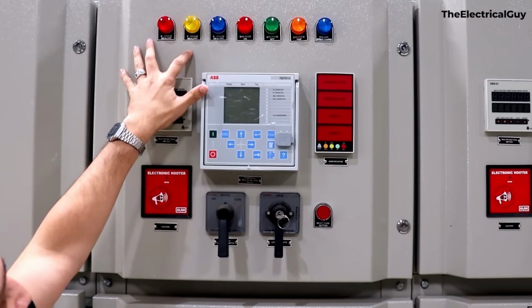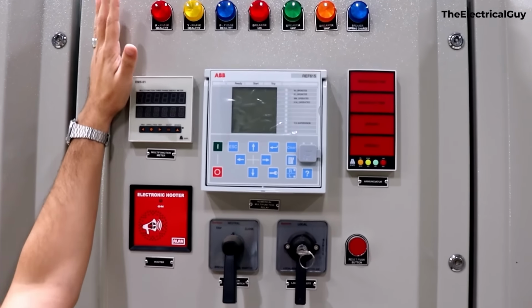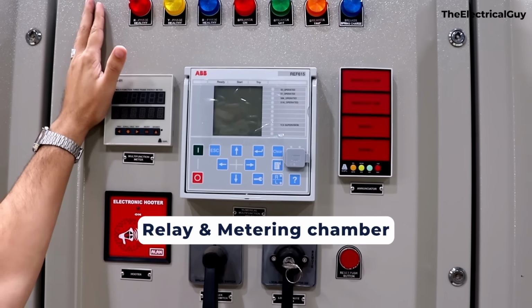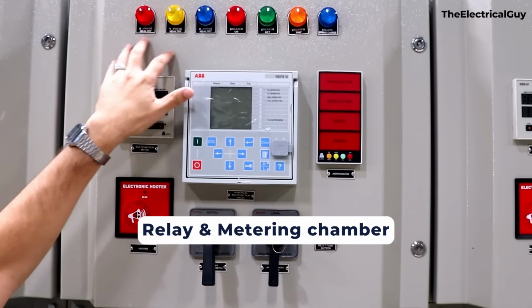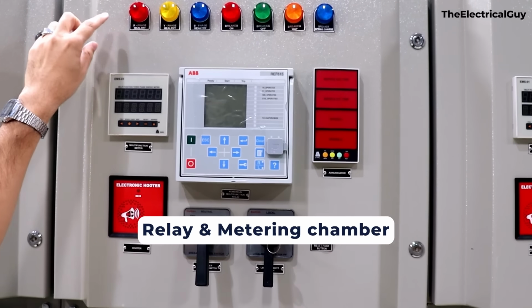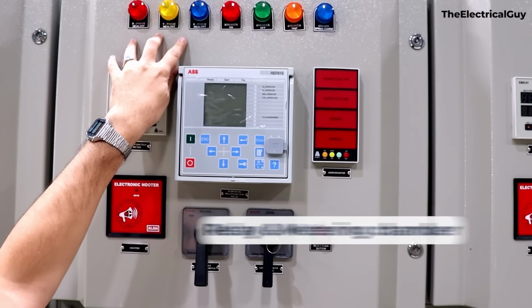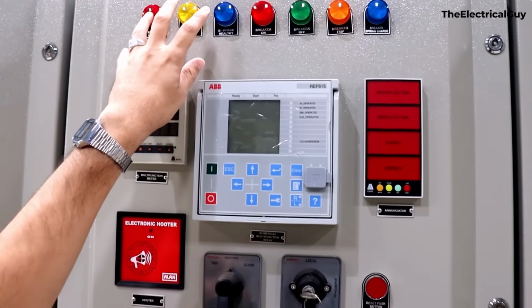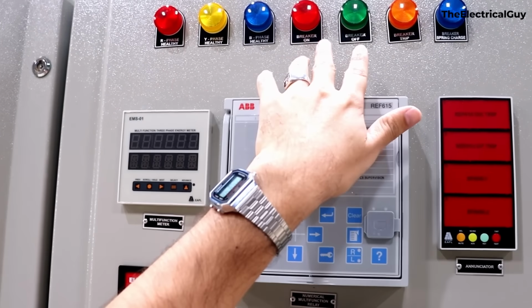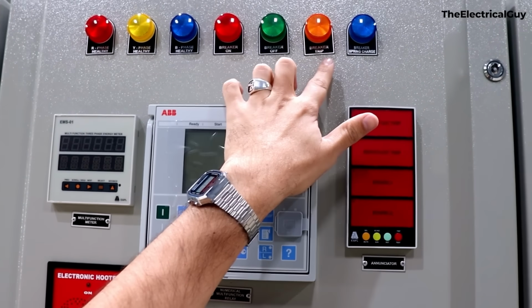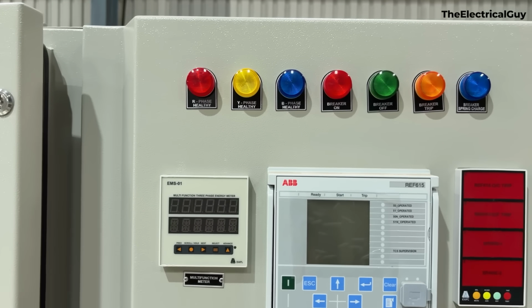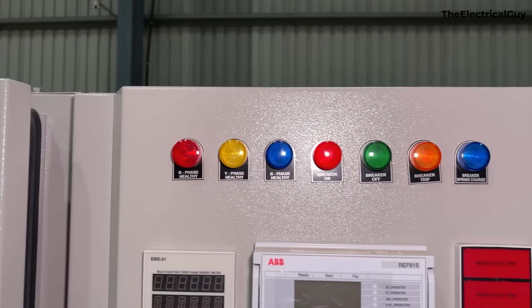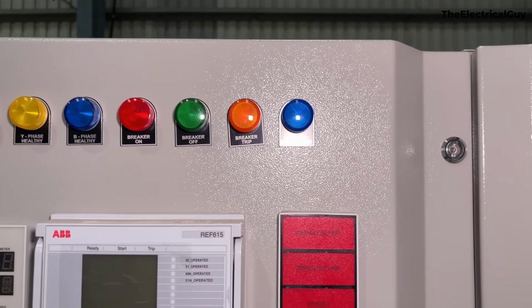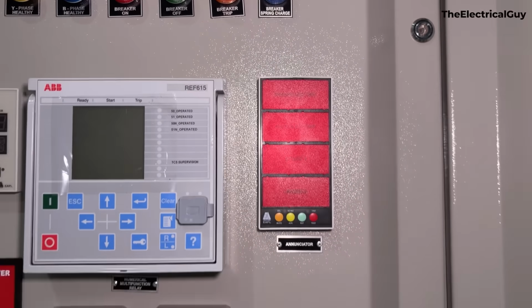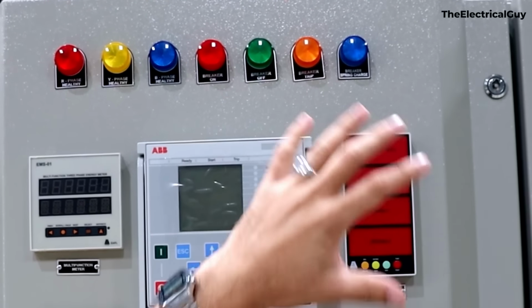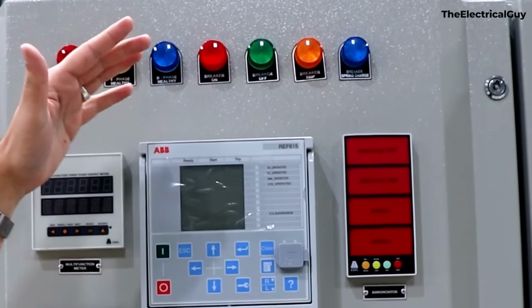Alright, so here are the indications, and before we go into the indications, this is also called the relay and metering chamber along with the low voltage chamber. So first you can see on top we have different indications. We have R, Y and B phase healthiness, so that means the voltage is available there and they are perfectly working fine. Then these are the indications about the breaker. In fact, the fourth also. You see the first one is breaker on, breaker off, and this is for breaker trip, and then breaker spring charge. So all these 4 indications are for the breaker, which is coming from the breaker's auxiliary switch to the low voltage side of the panel.